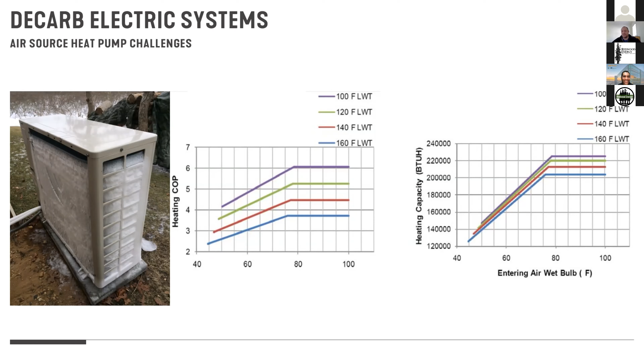Not just the COP, the coefficient of performance of the system, but on the graph on the right, you can also see the actual heating capacity of that system drops as well. The system has a limited capacity from the compressor and the size of the heat exchangers to extract a certain amount of heat. And as that delta T across the heat exchanger from the outside air temperature drops, the capacity of the unit is going to drop as well. And so these are the two things that we're fighting when we try to translate our electrification strategies to colder climates.